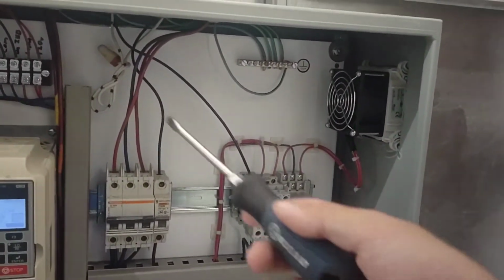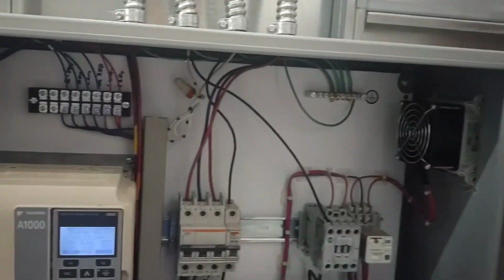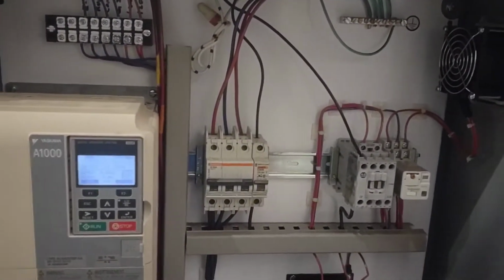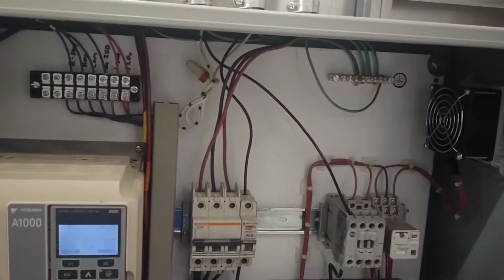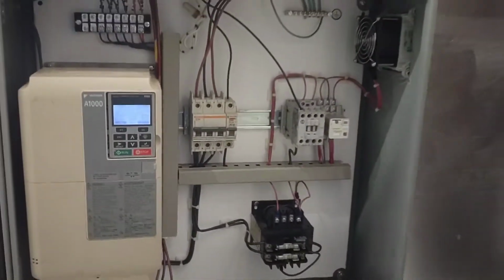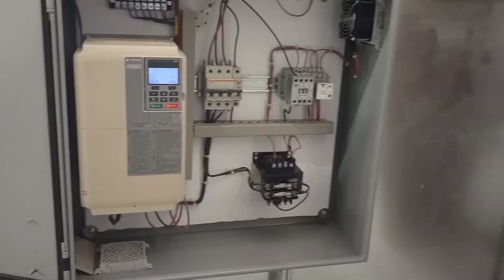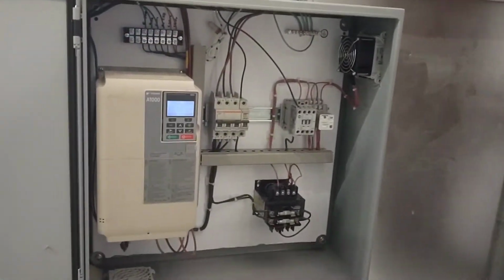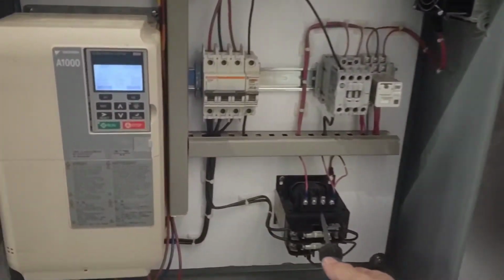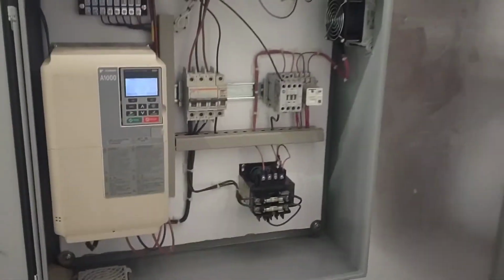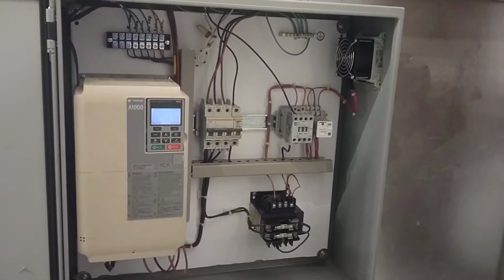I totally could have taken that 120 power from the lighting circuit, but if for some reason the lighting circuit trips and the VFD is still running on 480, then we're not going to have a fan and that's going to overheat. So I elected to have our own little 120 source just for the fan and the control light.